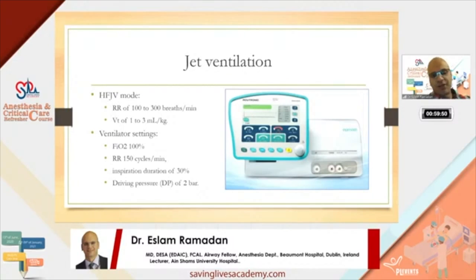This is the most common device that we are using here. It's the Monsoon device for subglottic high frequency jet ventilation. You can see here there's a button. This is the on and off button. This is what we call the laser button. It can be used also in laser surgery.